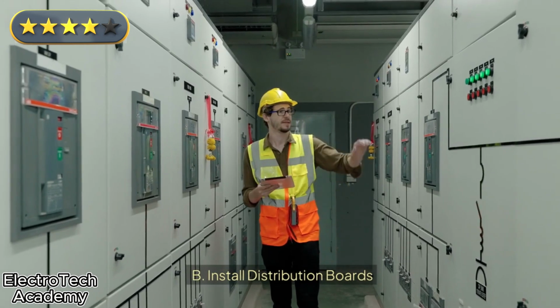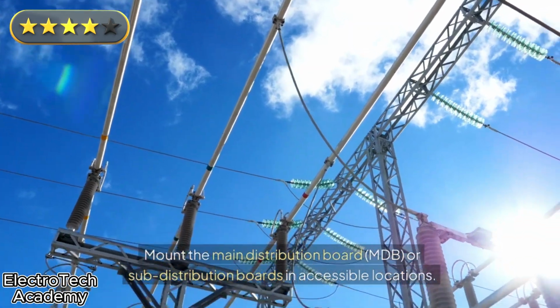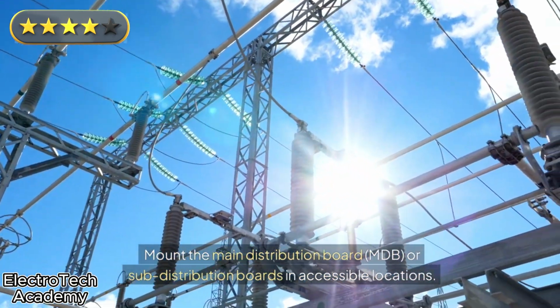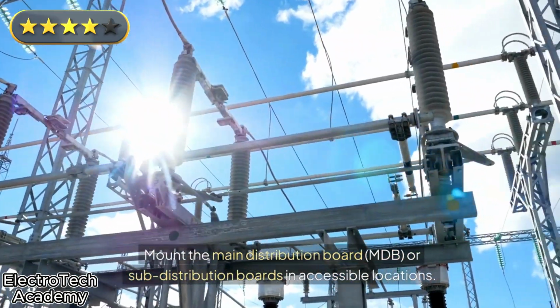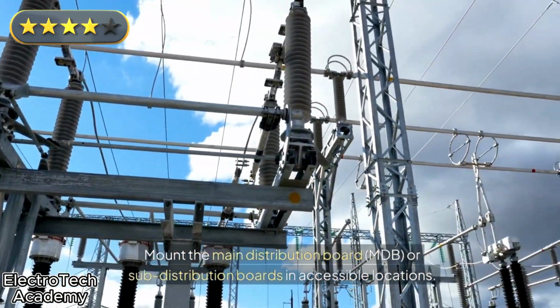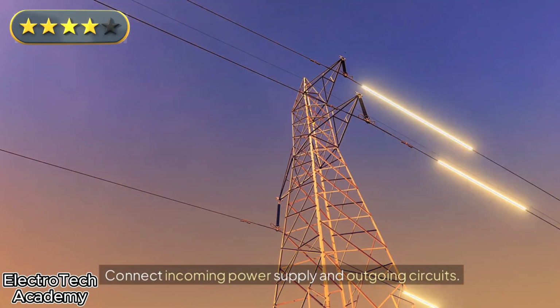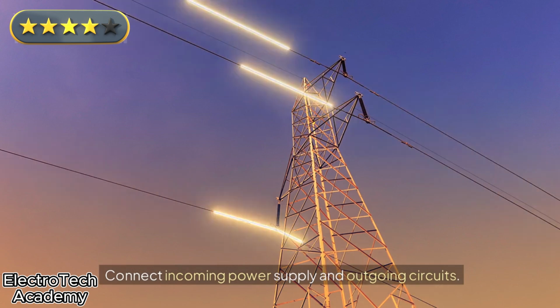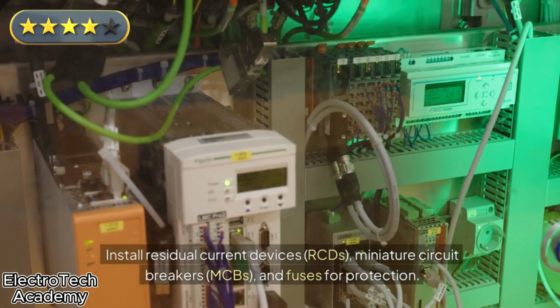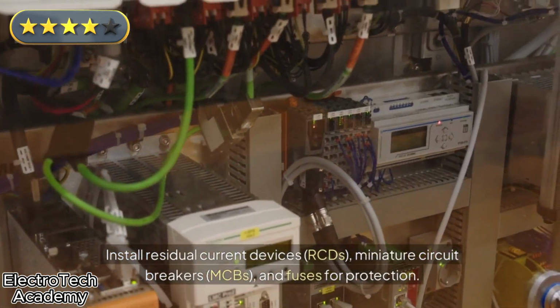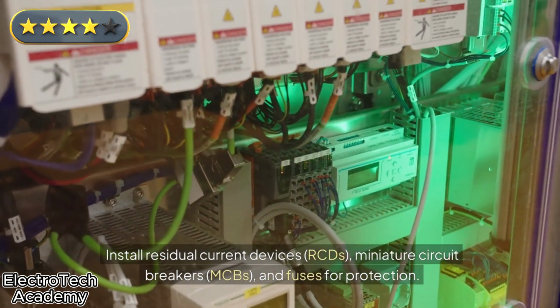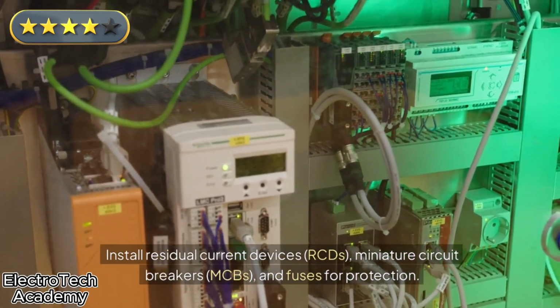B. Install distribution boards. 1. Mount the main distribution board, MDB, or sub-distribution boards in accessible locations. 2. Connect incoming power supply and outgoing circuits. 3. Install residual current devices, RCDs, miniature circuit breakers, MCBs, and fuses for protection.